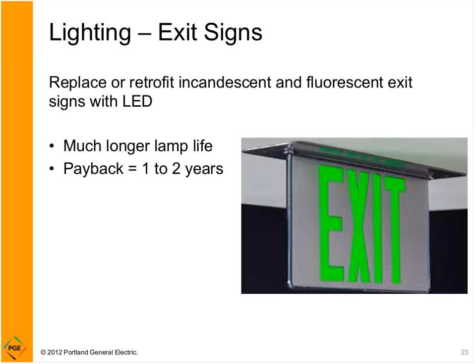Exit signs are another opportunity. If you have incandescent or fluorescent exit signs, you can either retrofit or replace the fixture with LED. LED is going to last 50+ thousand hours, compared to fluorescent, and it's only 3 watts. Incandescent is going to last probably a couple thousand hours and be at 40 watts. Fluorescent is a little bit better, but still about 18 watts and a 10,000 hour life. So much longer lamp life and significantly lower energy consumption.